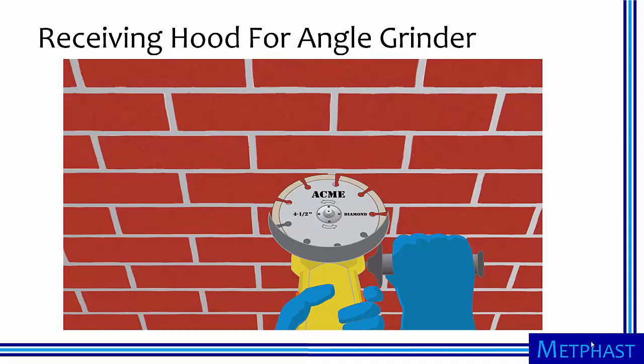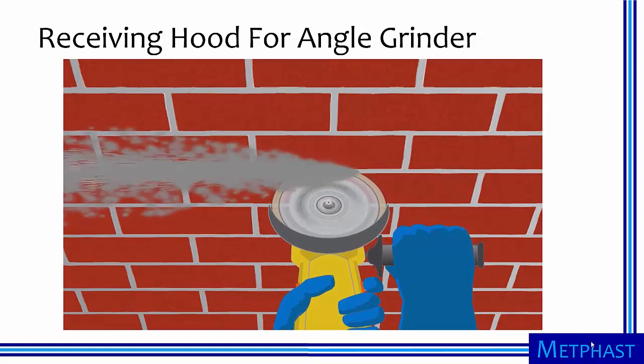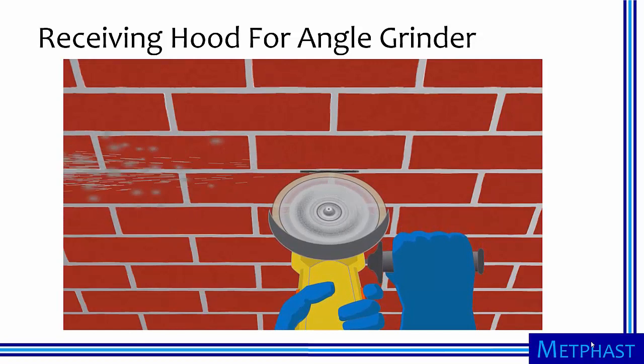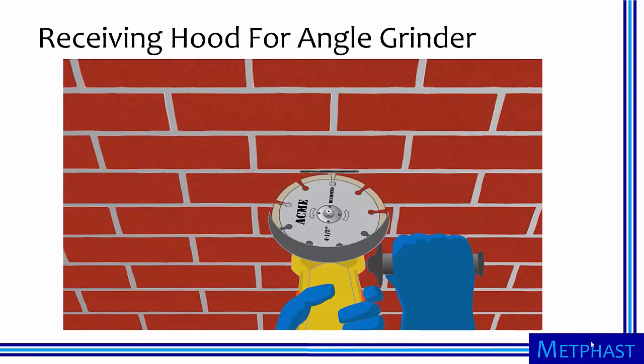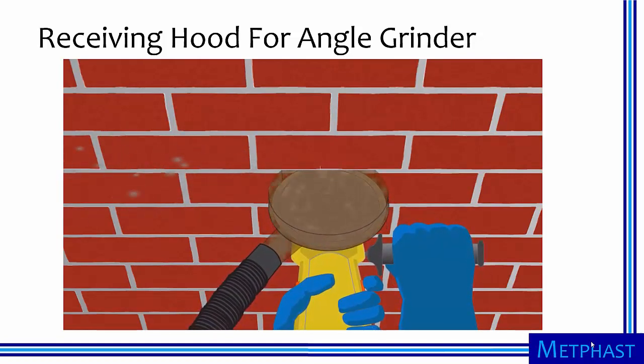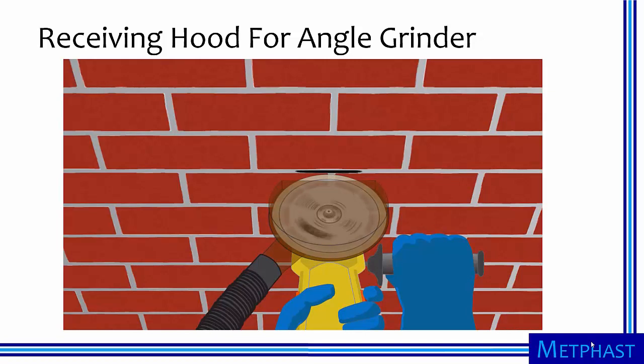The hood used to capture dust from an angle grinder is a good example of a receiving hood. In this case, a worker is using an angle grinder to remove mortar between bricks as part of a process known as tuck pointing. Without capture, the grinder throws debris and large quantities of dust into the air, often resulting in very high exposures to dust and, more importantly, crystalline silica from the sand in the mortar. A hood consisting of a shroud with a heavy-duty vacuum can be used to dramatically reduce dust exposures. The shroud is specially designed with the vacuum positioned to receive the dust as it is thrust into the air by the inertial energy of the grinding wheel.